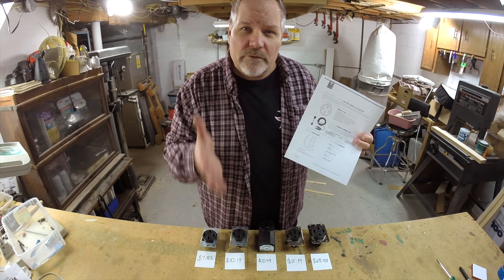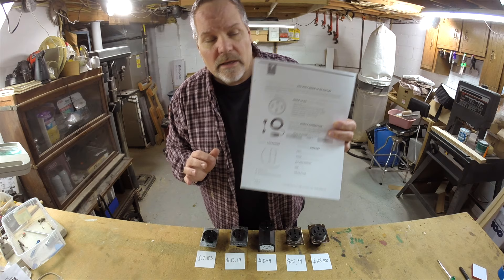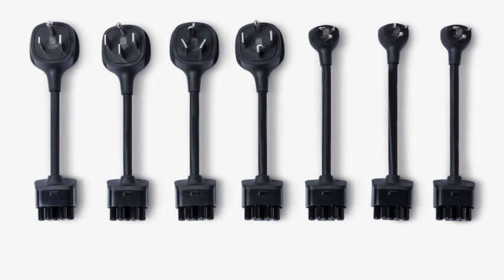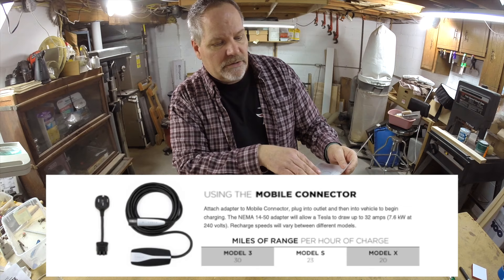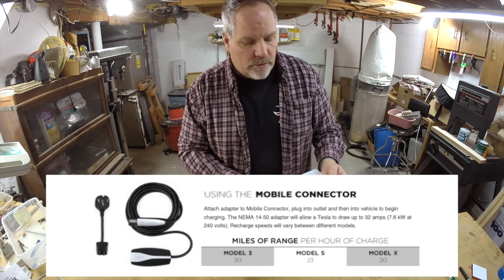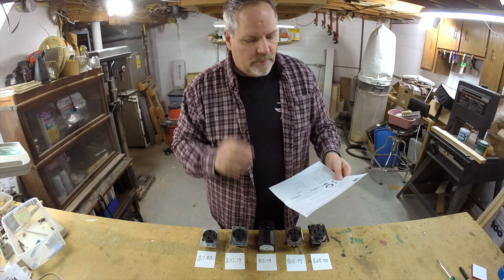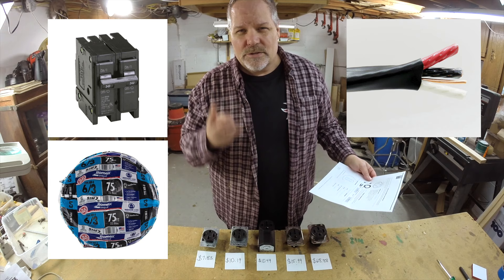Tesla is pretty good about giving you information about how to install an outlet for charging. This is the document about the NEMA 14-50 plug — a popular plug. There are actually eight different options you can plug into the UMC, and which one you use determines how fast it charges your car. For the Model 3 you can get 30 miles per hour of charge rate, Model S is 21, and Model X is 20. Tesla specifies a 50-amp circuit breaker and six-gauge wire — specifically six/three wire, meaning three conductors.